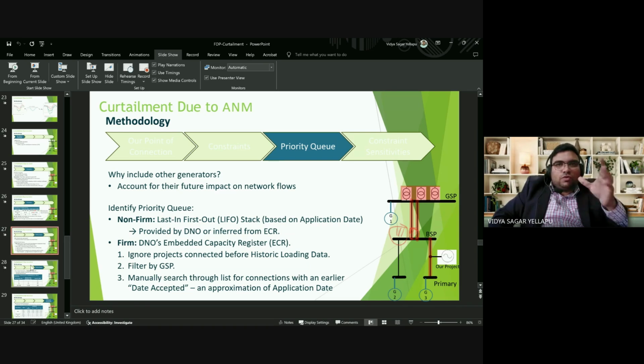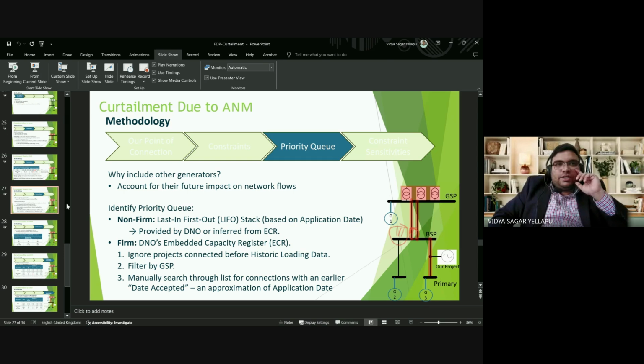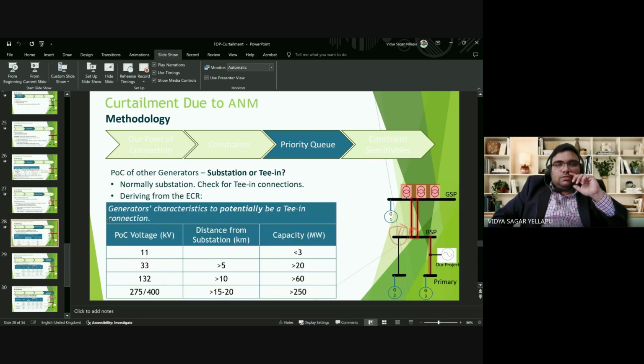So there is the overloading, that means historical loading is there. If projects are connected in the LIFO stack before the historical loading data we got, then there is no need for those projects to be added to the assessment. For each of these GSPs, or grid supply points, we need to look at all the projects that are getting connected, and ignore all the projects connected before the historical loading data. The rest of the projects can be sorted based on the date accepted. That gives us an indication of this priority stack. And after getting that priority stack, we can find the LIFO stack for a particular project.